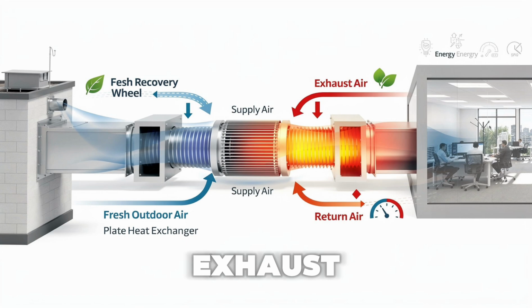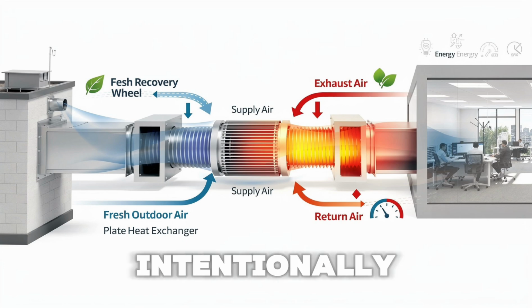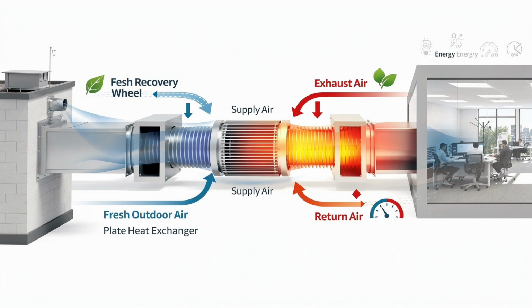Step 3. Heat recovery section. The fresh outdoor air and the outgoing exhaust air pass through a heat recovery device, such as a heat recovery wheel or plate heat exchanger. Heat energy is transferred between the two air streams without intentionally mixing them. This reduces the load on the cooling or heating system and saves energy.